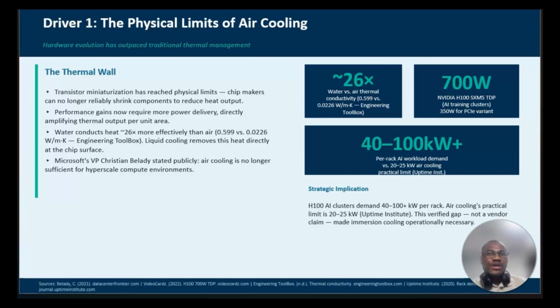The NVIDIA H100 GPU powering most AI training today has a thermal design power of about 700 watts in its server configuration, and AI workload racks now demand between 40 and 100 kilowatts of cooling capacity. Air cooling practically limits to 20 to 25 kilowatts per rack. The gap is not a minor engineering challenge, it's a fundamental mismatch. Microsoft's own VP of data center development, Christian Belady, said it plainly: air cooling is not enough.